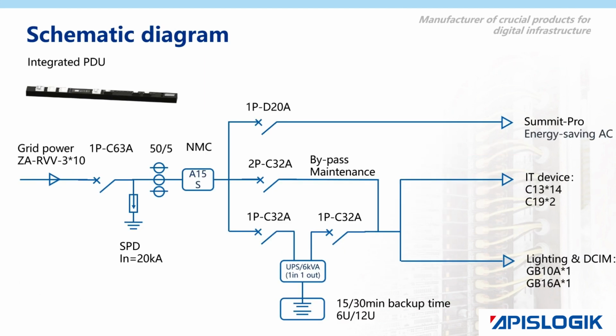Schematic diagram of a 6K micro DC and the integrated PDU. Single-phase mains power connection with circuit breaker protection. The PDU has input and branch monitoring functions. Power is divided into 3 circuits. One circuit supplies power to the AC, another circuit supplies power to the IT equipment, and the third circuit supplies power to other devices such as lighting and DCIM.